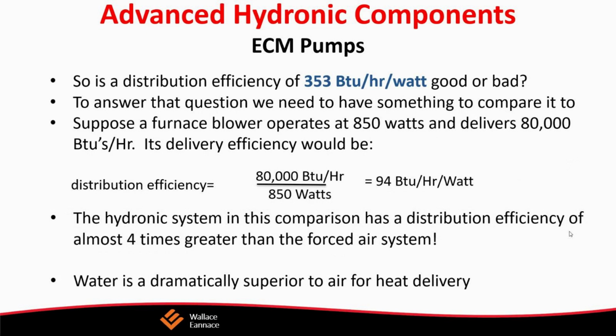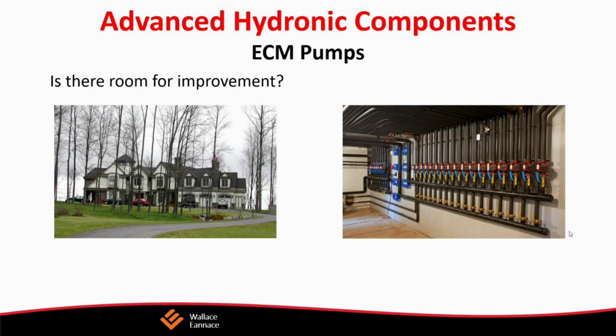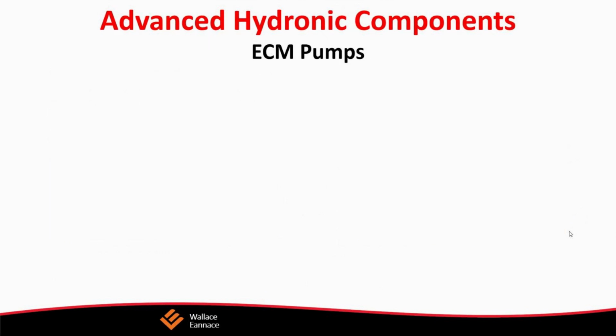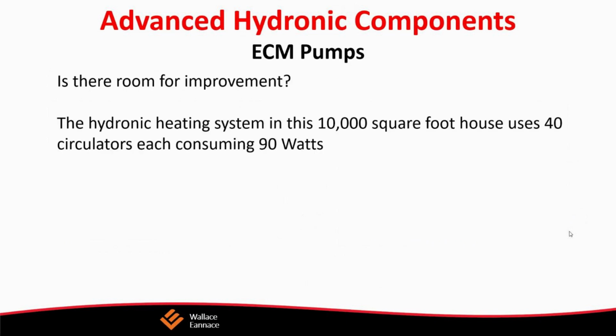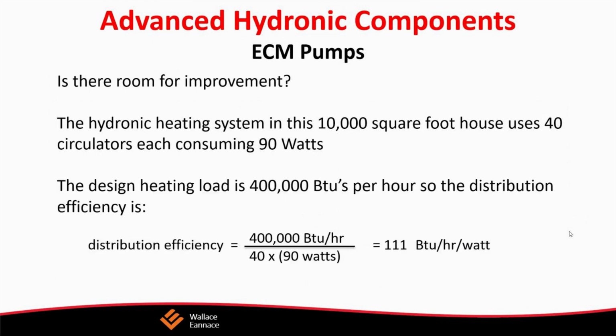So let's consider a system that delivers 120,000 BTUs per hour at design load conditions using 4 circulators at 85 watts each. We would have a distribution efficiency of 120,000 BTUs per hour divided by 340 watts. That gives us 353 BTUs per hour per watt. So, like I said, we're trying to determine how well we distribute the heat within a heating system.